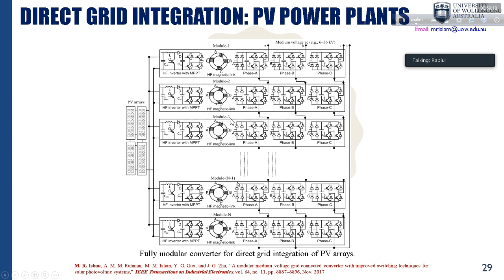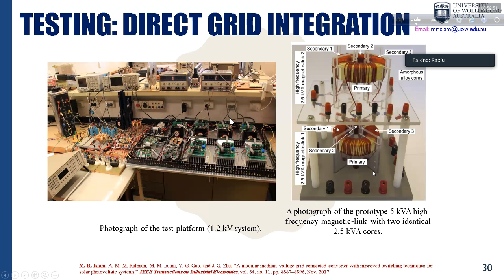That means our converter should step up the voltage from low voltage to medium voltage and also provide galvanic isolation. This high frequency magnetic link can ensure those things, and the power handling capacity is not a problem because by increasing the number of modules, we can increase the power handling capacity of this type of technology.